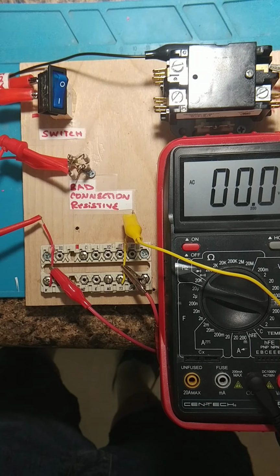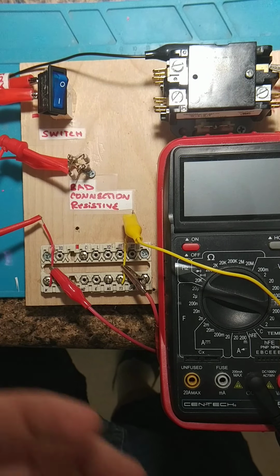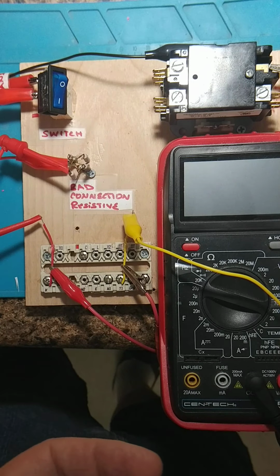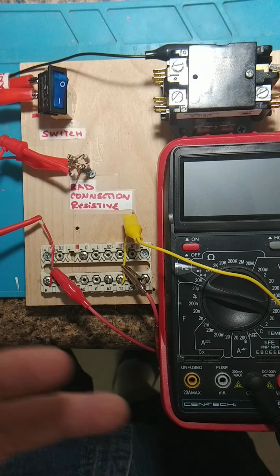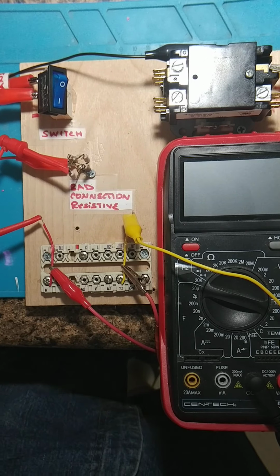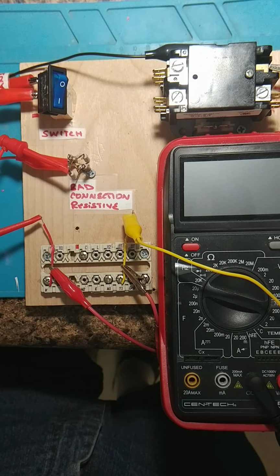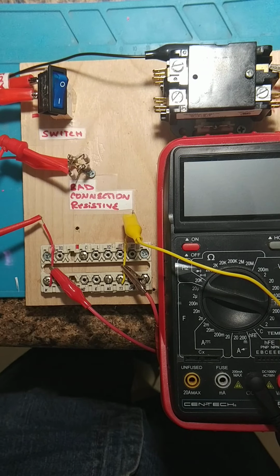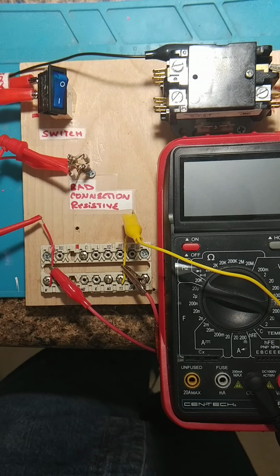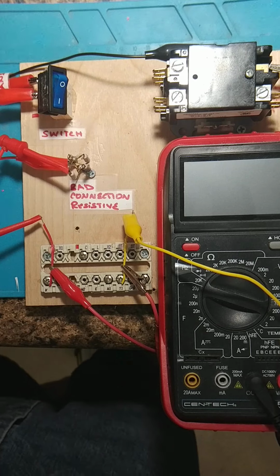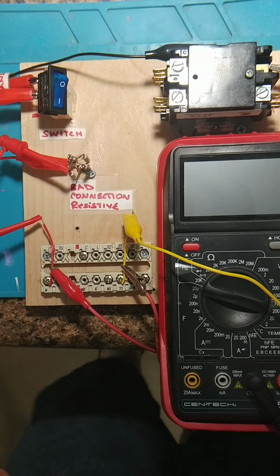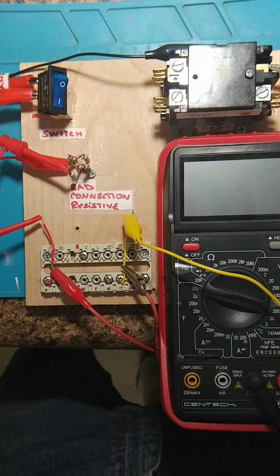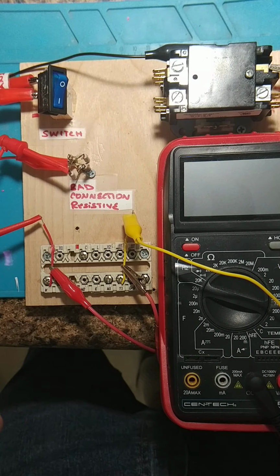Or they may have it at the bottom of the suction line where they've just spliced it together, taped it up, and it's there near the outdoor unit, and it's just over time gotten really rusty. Or it could be where the thermostat wiring comes up through a gooseneck on a roof. The wires were spliced there, and so you really are just going to have to trace out and check all your wire connections and make sure that those are good.